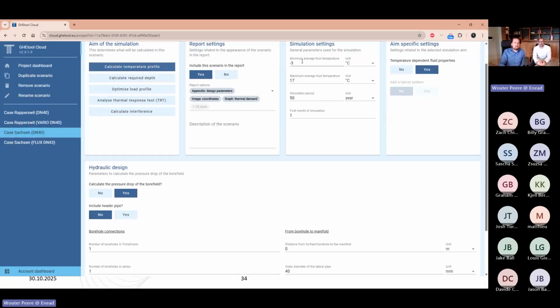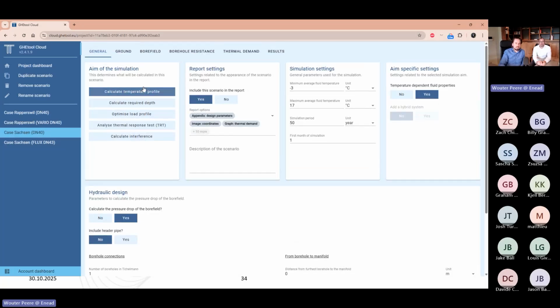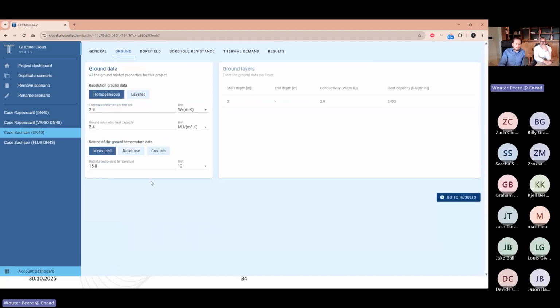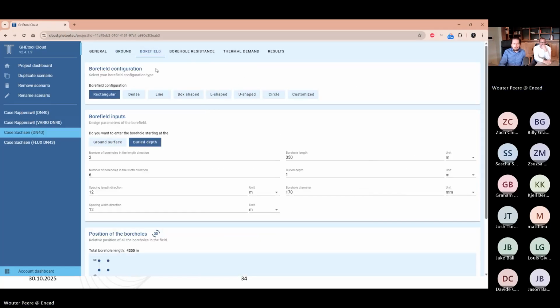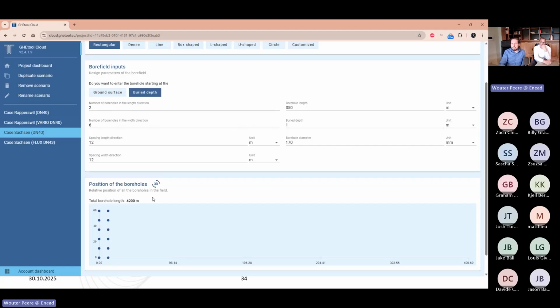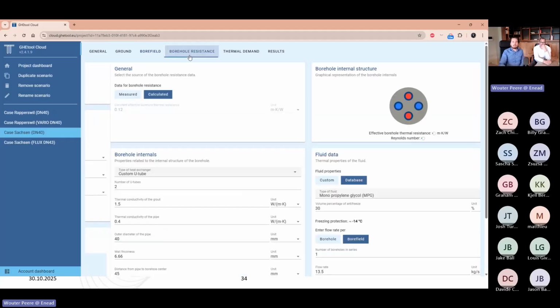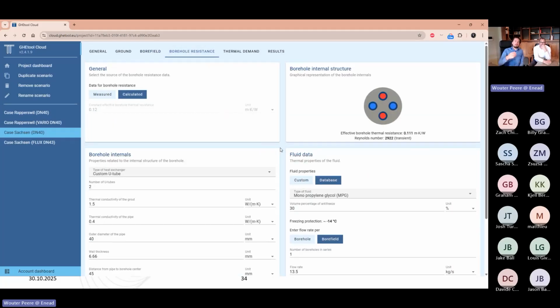Same thing here. It was a different region, different design parameters. Here it was -3. On the ground, a TRT test was done, so we just entered the undisturbed ground temperature directly, and our conductivity. We now have 2x6 boreholes, so 12 boreholes of 350 meters length. For our borehole resistance, in comparison to this case, of course, there is no regular PN32 probe. So we created a theoretical one, with a DN40.